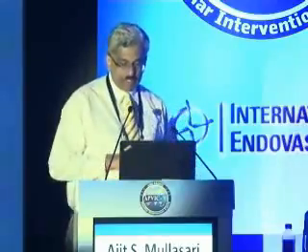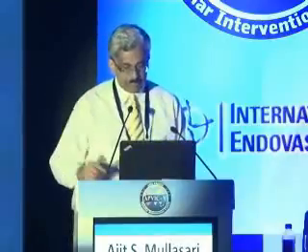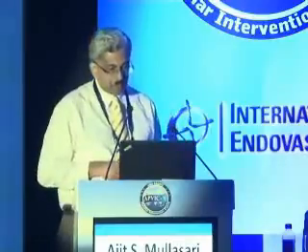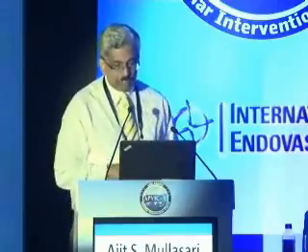This is the Boston Scientific filter. It is a 3.2 French device. It fits only 3.5 to 5.5 millimeter vessels. It's preloaded with a 110 micron pore. The Spider is a very useful device because you can pass a coronary wire in parallel, 0.014. It's a preloaded filter and 6 French compatible.